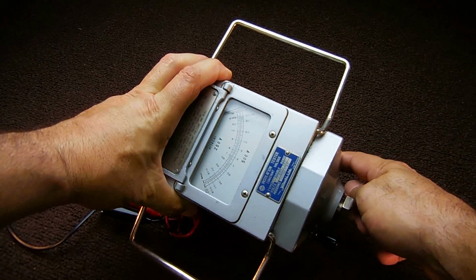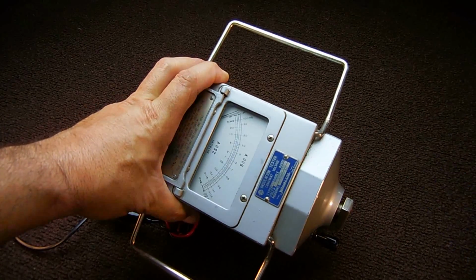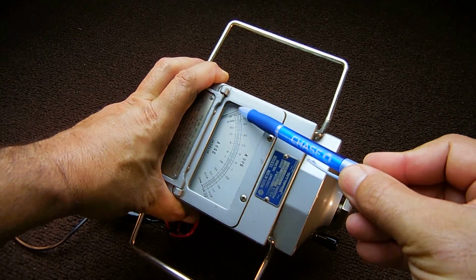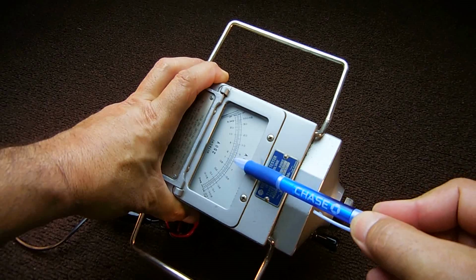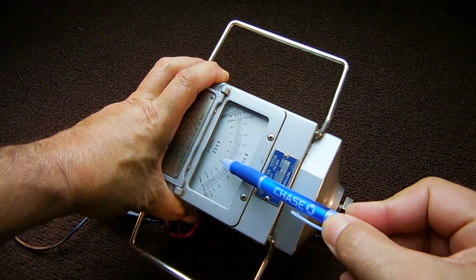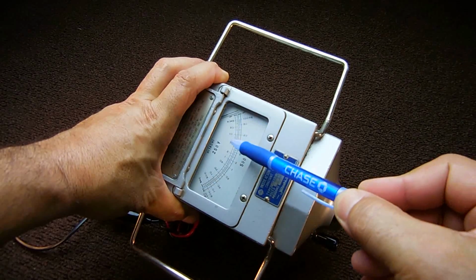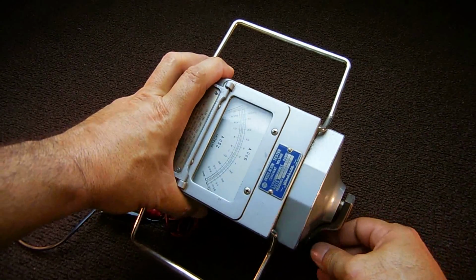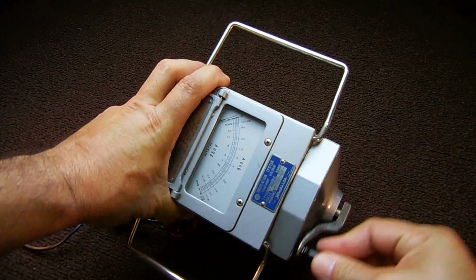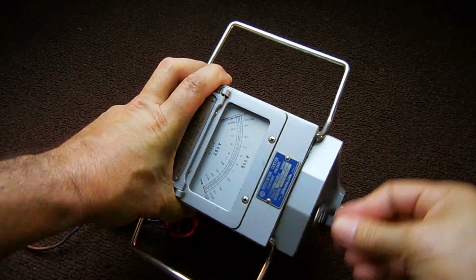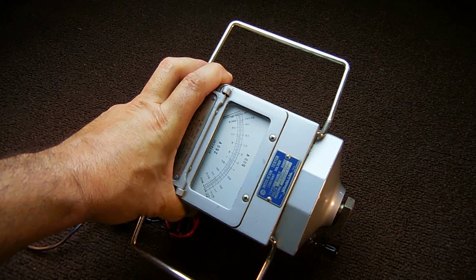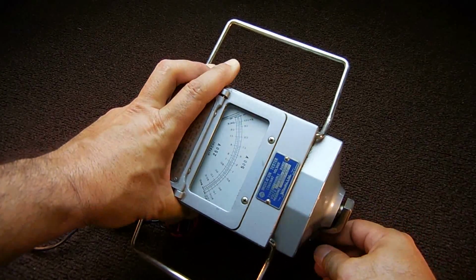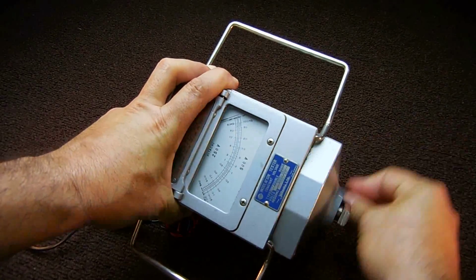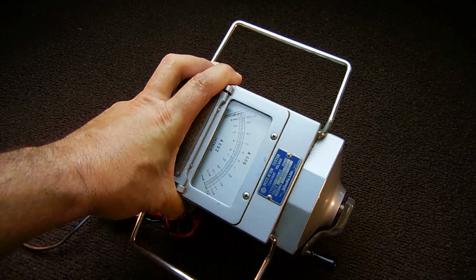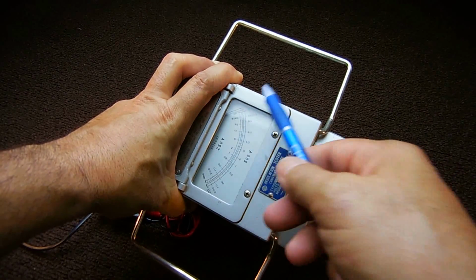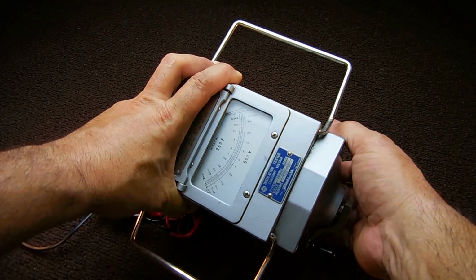Put this on the 250 volt setting. Alright, it's on 250. If this wire had faulty insulation, you would see it swing all the way down over here on the 250 volt range to the 1-2 meg and below. So let's make sure it stays as high as possible. And you can see there's nothing going on. It moved back again. That's well above the 100 megohm. It's probably in the thousands of megohms. Now if I push it up to 500, let's see what happens.